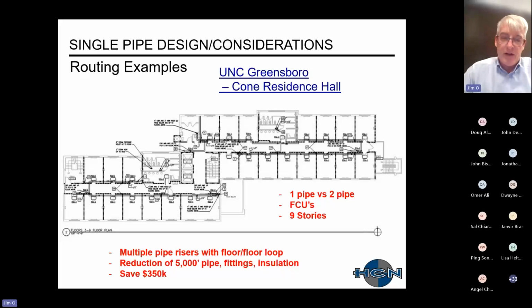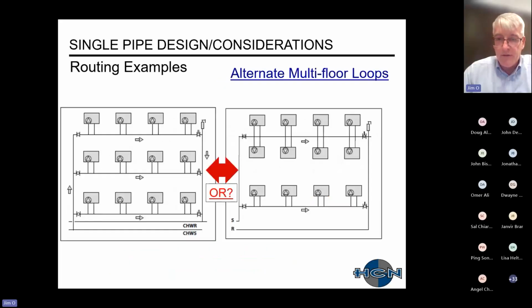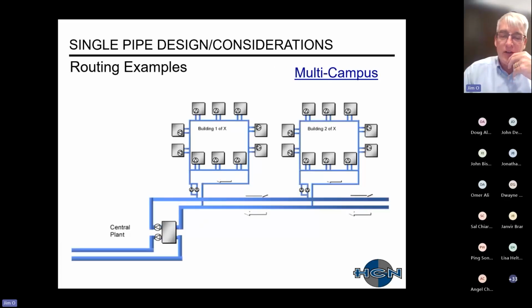This was actually a case study where they looked at the reduction in piping to go from a two-pipe system to a one-pipe system. You can see it saved an enormous amount of piping, 5,000 feet, and this turned into a savings of $350,000 on their first cost. Other examples are alternate multiple floor loops. Here's a multi-campus one where you have a central plant, you have a main, and then each of the buildings has their own loop. And then from the loop, there are even more loops, et cetera.